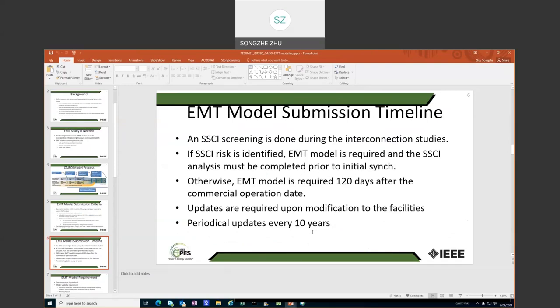And the timeline already kind of covered. So we run the SSCI screening at the end of the interconnection study phase. If there's no SSCI risk, the model is required 120 days after the COD. If there is a risk, the model is required before it can synchronize. And whenever there's a modification, models are required to be updated. Also, we have a periodic update of all the models every 10 years.